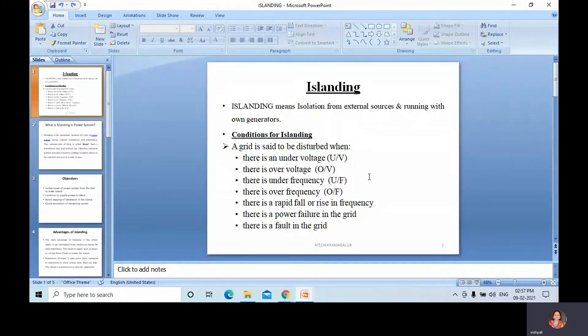A grid is said to be disturbed when there is an under-voltage or over-voltage, or when there is an under-frequency or over-frequency — a rapid fall or rise in frequency — or a power failure or fault in the grid. These are the conditions for islanding.